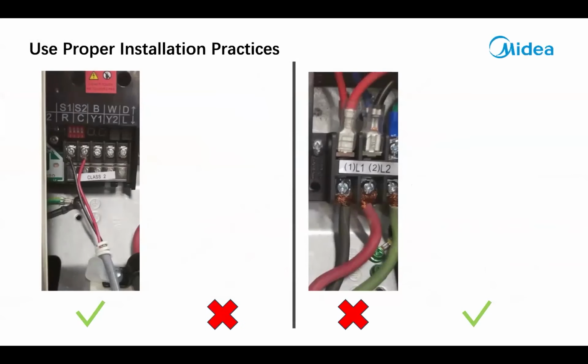Wire connections, proper practices. On the low voltage or the communication, we are okay if you take that stranded wire, not twist the wires together, but twist the strands of the cable, and stick it under that T screw and tighten it down. Just don't over torque it. We're not, however, okay with L1 and L2 being done that way. Everybody understand that right there is going to cause a problem down the road.